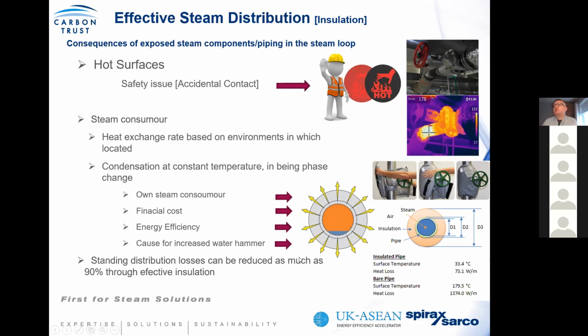But from an energy perspective, you need to consider that these exposed pipes not only radiate heat to the atmosphere, but the steam distribution system, in some cases, can be one of the biggest single steam consumers. Although you're serving steam to the end user, your distribution system runs 24/7 so long as the steam system is primed. The process may operate on and off, but your steam system is continuous.